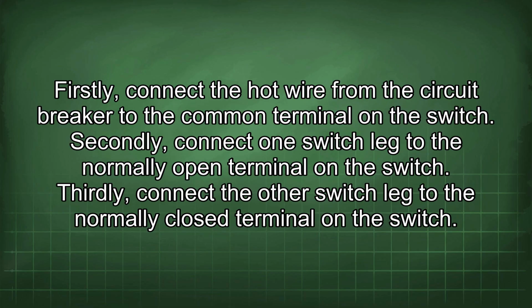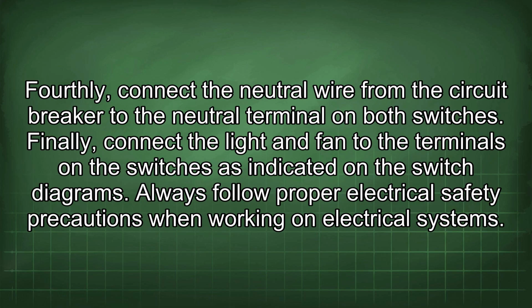Firstly, connect the hot wire from the circuit breaker to the common terminal on the switch. Secondly, connect one switch leg to the normally open terminal on the switch. Thirdly, connect the other switch leg to the normally closed terminal on the switch. Fourthly, connect the neutral wire from the circuit breaker to the neutral terminal on both switches. Finally, connect the light and fan to the terminals on the switches as indicated on the switch diagrams.